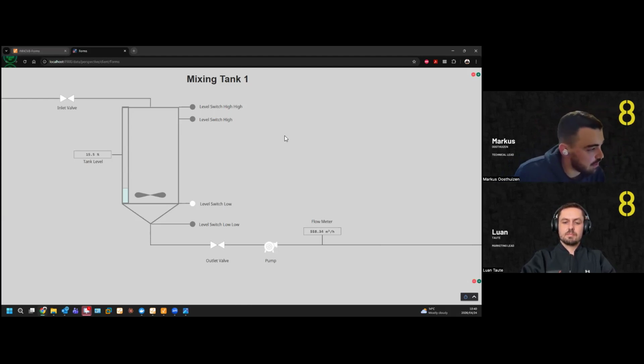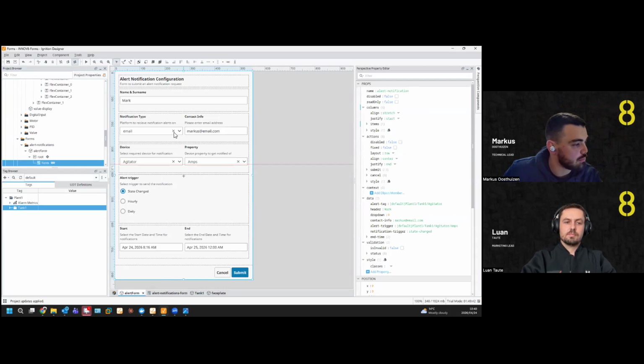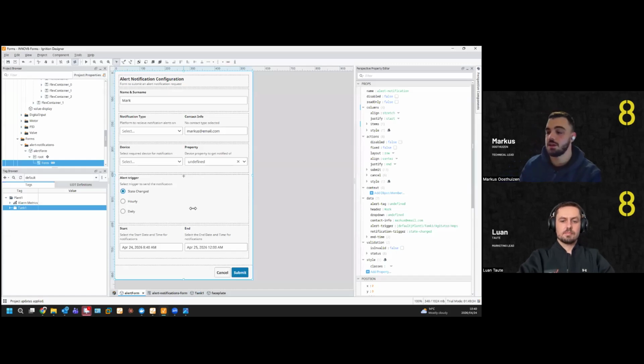For example, this form that we built today will not work the way you want it to in offline mode. The reason for that is the bindings that we've got on the form, especially the ones that do the tags. Unfortunately, bindings do not fire offline at all because bindings fire on the gateway. So the bindings cannot talk to the gateway, so they can't fire.